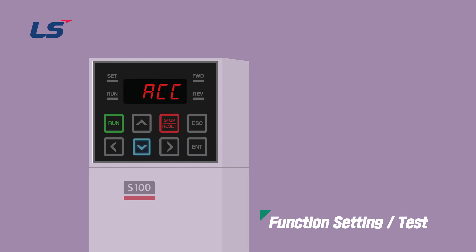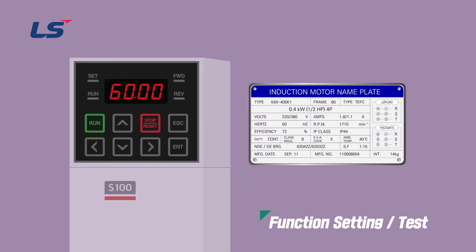The following explains how to input the information on the motor nameplate into the inverter. If you look at the motor nameplate, there are information such as motor capacity, rated voltage, rated current, and motor efficiency. When looking at voltage and current, if the input voltage is 220 volts, the rated current is 1.8 amps.